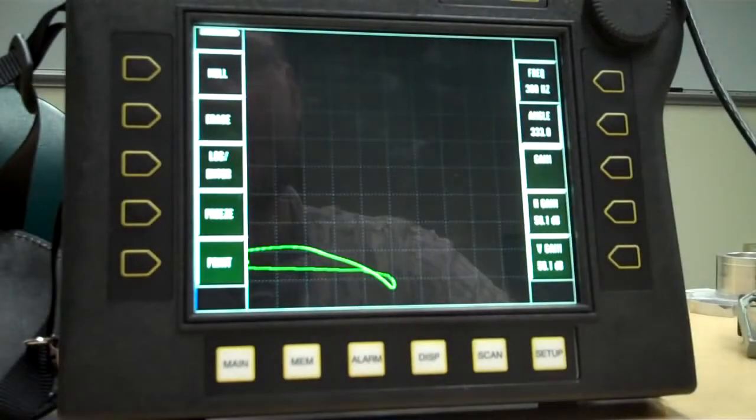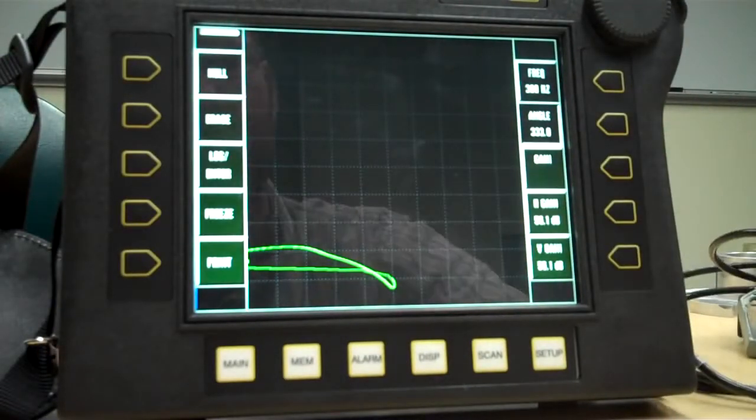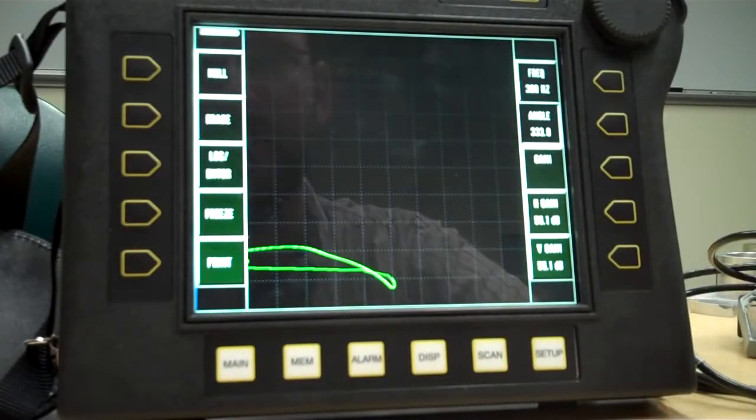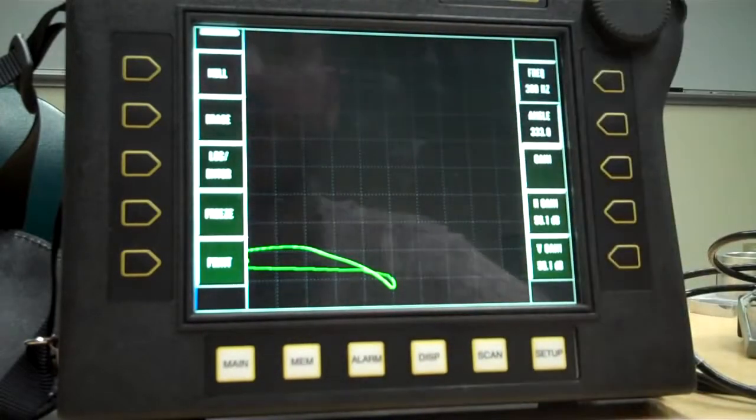Whereas when we took the frequency and raised it up and we were around 3 kilohertz, we saw a nice big spread here for all those different thicknesses because we were pretty much set for that standard depth of penetration. So just something to think about when you're testing your frequency and what that actually does with your conductivity curve or what that does with your thickness line.